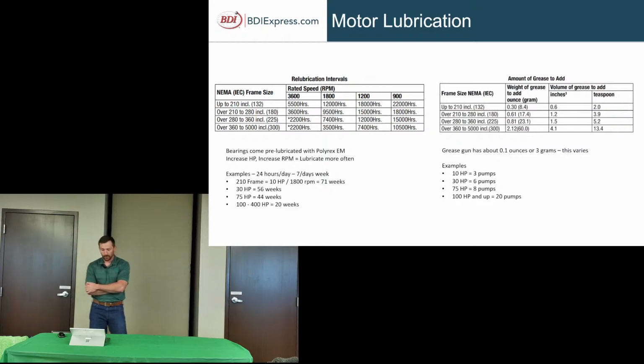But for example, on a 210 frame, 10 horsepower motor, which you guys probably see a lot of, typically 1800 RPMs. Some of you might be working with 3600 RPMs. But that's going to be 3 pumps and lubricating it every 71 weeks. And then as you go higher on your horsepower rating, you're going to be lubricating it more frequently because it's bigger and the bearings inside are bigger as well. I'll go to the next slide here.